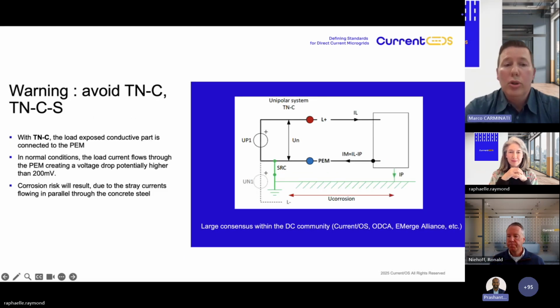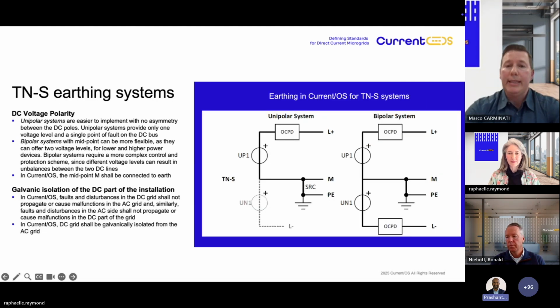So TN-C and TN-C-S systems are also not recommended, for the same reason. In particular, here in a TN-C system, the load exposed conductive parts are connected directly to the PEN conductor. That means that also in normal condition, the load current flows through the PEN, creating for sure a voltage drop, which is usually higher than 200 millivolts. So also in this case, even with a higher probability than TT, we can have a risk of corrosion.